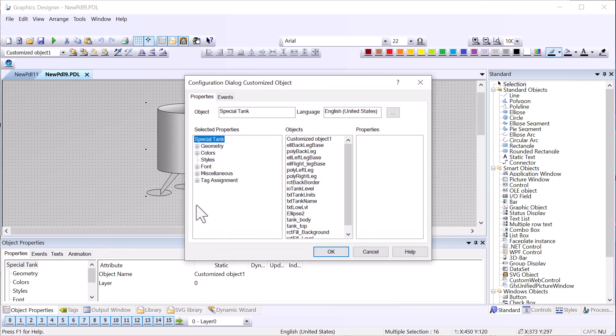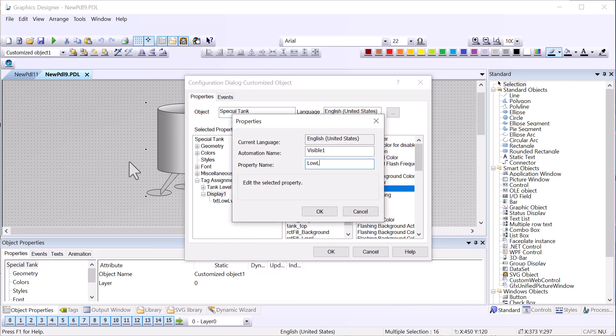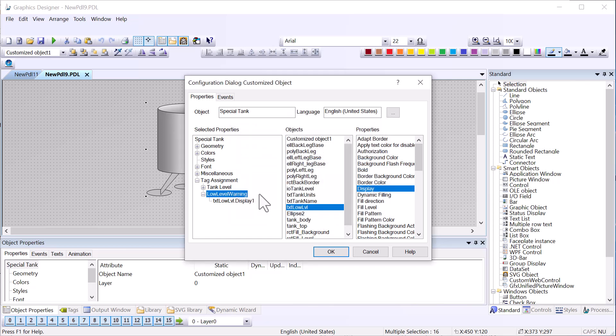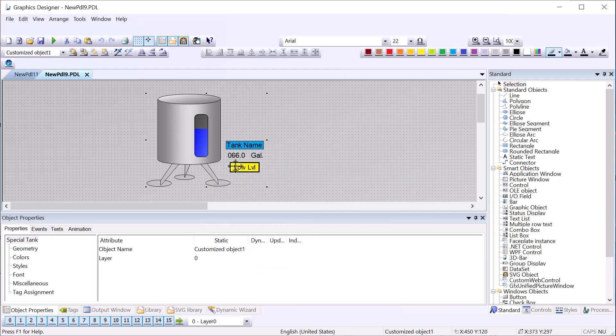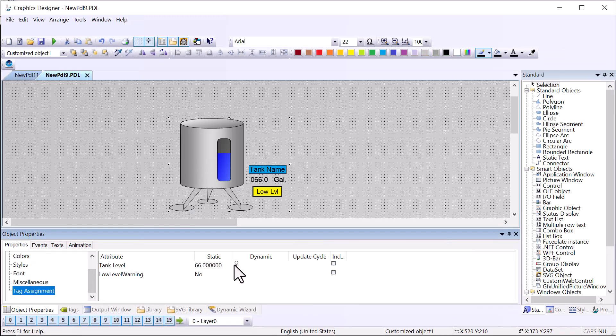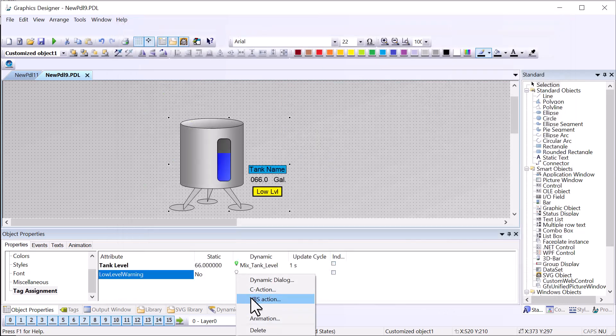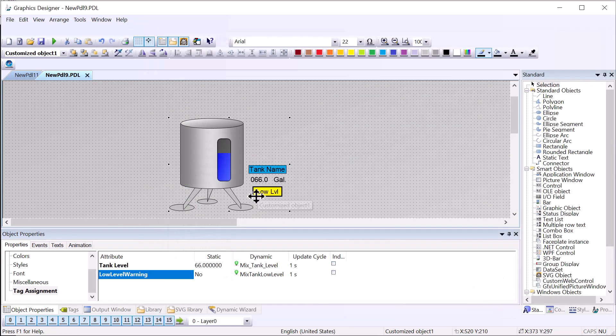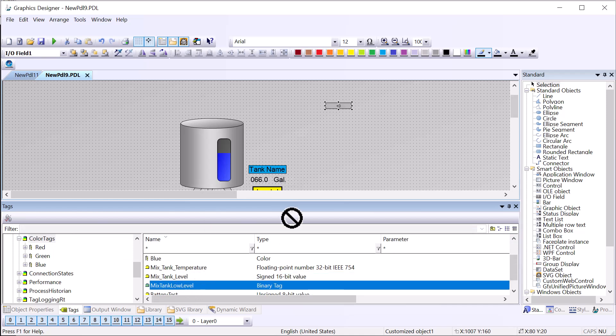To get out of edit mode I'll lasso everything — make sure your cursor is over something that's selected — then right-click, Customize Object > Finish Editing. Now when we go into our Configuration Dialog we have our text_low_level component. For Tag Assignment I'll get the Display property of the low level indicator, drop it under Tag Assignment, and call this 'Low Level Warning'. That's a boolean property, so if this goes high it's going to show the indicator.